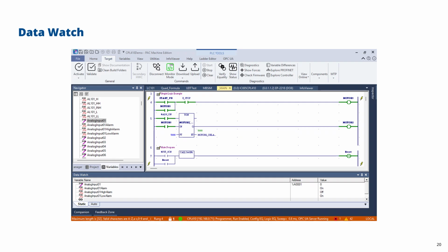Now that's dangerous because you could turn on an output, and if the force remains, the output will remain on even if any interlocks try to stop or turn off the output. But it's a good way of testing applications, you just need to be a bit careful on that one. You can't force analogs, at least not directly from the data watch window, but what you can do is use the analog input function blocks. They do support forcing, so there is a way of forcing analog inputs, but you have to do it through a function block. Or you could also implement your own override logic using function blocks in the logic, and you could have an analog input actual and an analog input force, along with a bit maybe which toggles between the two. So there are ways of forcing analogs, but it requires a bit more work and a different approach. But Booleans can be forced.